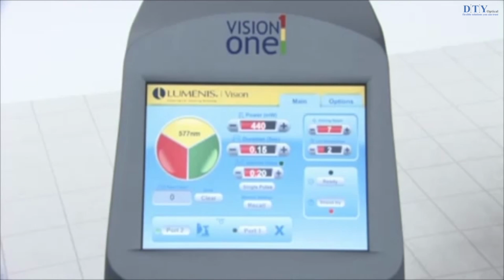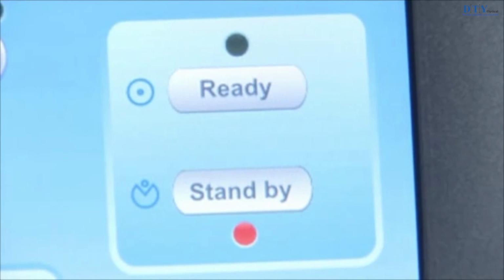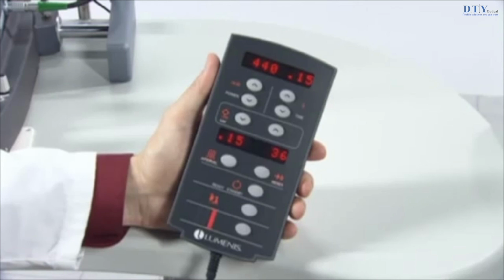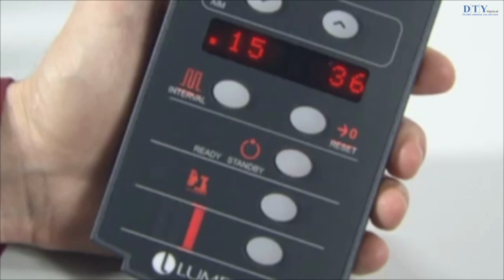If any fault conditions are encountered during the laser self-test and warm-up, refer to the troubleshooting guide in the maintenance chapter of your operator's guide. When the laser is powered on, the laser emission indicator displays on the control screen to provide a visual warning that the laser energy is accessible. The indicator continues to display until the laser is turned off. When the remote control is connected to the laser, the Ready Standby selector illuminates to provide an additional visual warning that laser energy is accessible.